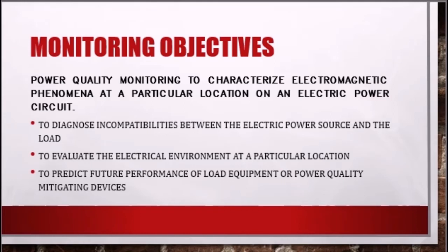The objective of monitoring for a particular project determines the choice of monitoring equipment, the method of collecting data, the triggering threshold needed, the data analysis technique to employ, and the overall level of effort required of the project. The objective can be as simple as verifying steady-state voltage regulation at the service entrance or as complex as analyzing the harmonic current flow within the distribution network.